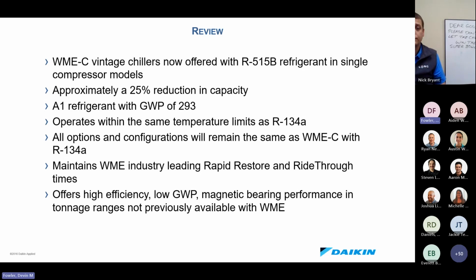All options and configurations will remain the same within the WME-C vintage compressors. We will still offer low harmonics, rapid restore and ride through, inverter operation. You're not going to lose any of your operability within the machine itself or any of our offerings. Still, we'll keep that industry leading rapid restore and ride through time as we transition to 515B. But now what we have is a high efficiency, low GWP magnetic bearing chiller with that magnetic bearing performance and tonnage ranges not typically offered by WME. It's tonnage ranges we didn't have previously available.